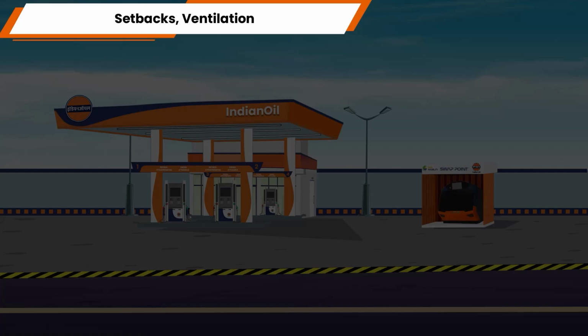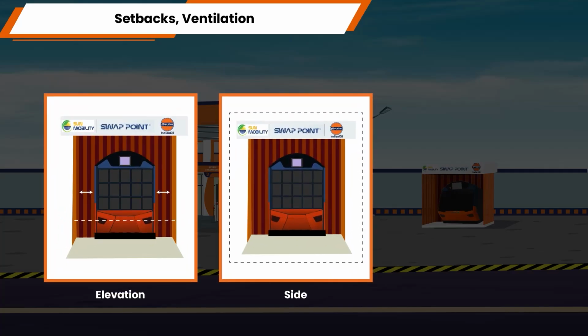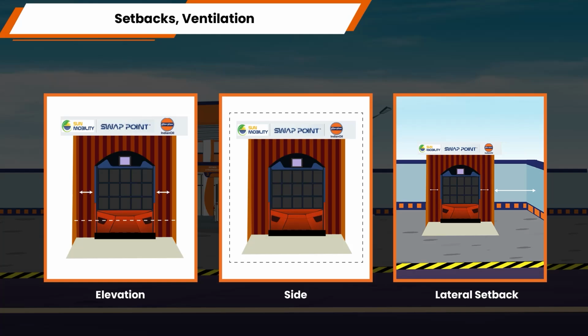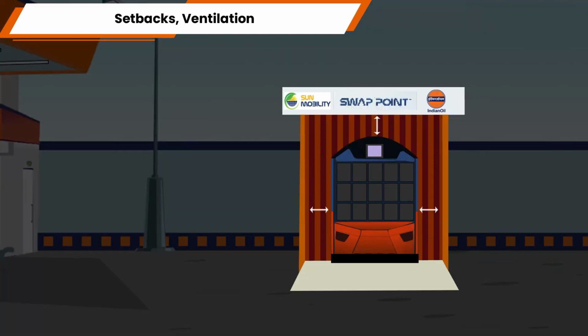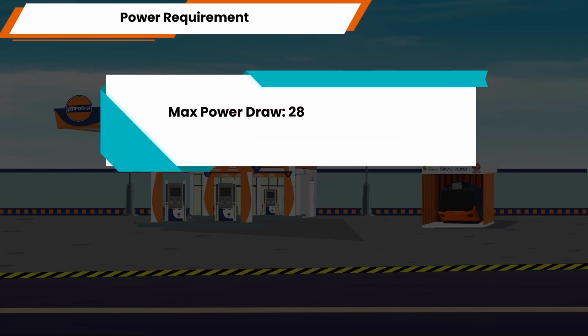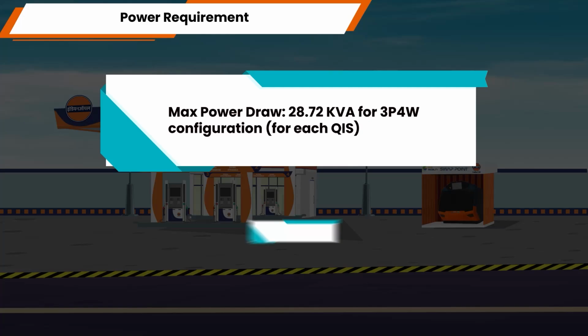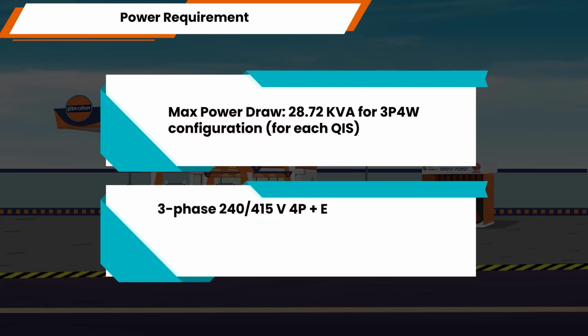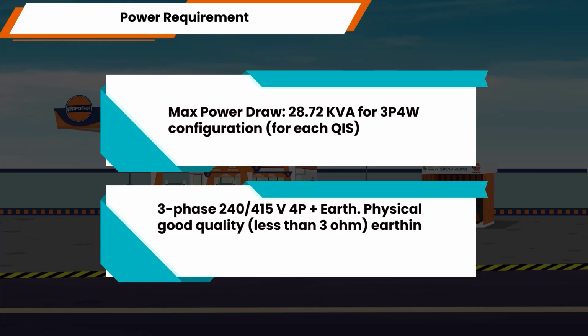The QIS is anchored to the concrete blocks with minimum M10 by 100 mm anchor bolts under each of its corners. Setbacks. Ventilation. Elevation, side and lateral setback is recommended. The minimum ventilation area around the QIS is recommended. Power requirement. Max power draw 28.72 kVA for 3P4W configuration for each QIS. 3-phase 240 by 415 V, 4P plus earth. Physical good quality less than 3 ohms earthing mandatory.